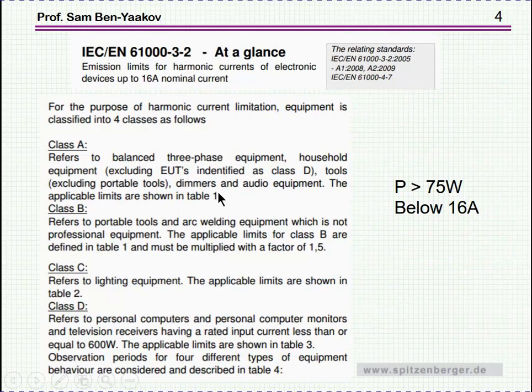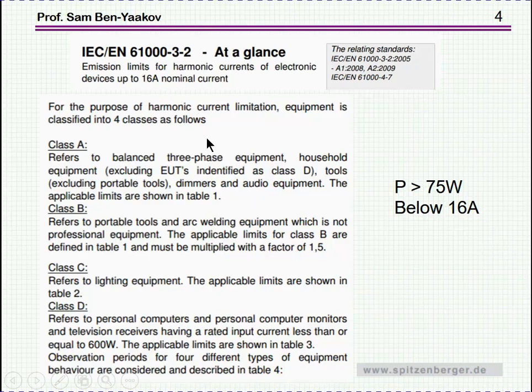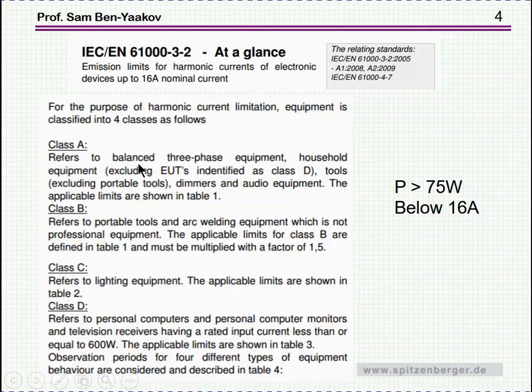As I've already pointed out, manufacturers are required today to make sure that the harmonics of the current injected into the line will be below a certain limit, and these limits are defined by the standard or norm. This is an example — the IEC or EN 61000-3-2 — which specifies exactly the type of equipment it relates to and the limits of the harmonics.